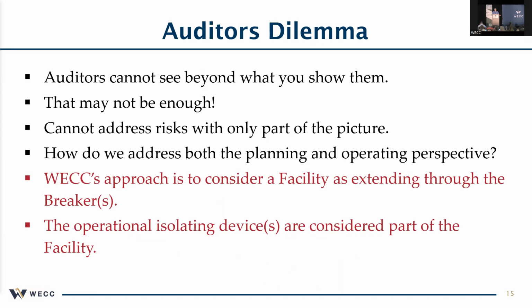Auditors don't get a comfortable feeling if you say, well, this is the rating that we're providing and it's only going halfway down this line. Do you agree with your partner? Is that the real rating? Does a person on the other end have a different rating? So our process in WECC, and I think the rest of the regions are, in fact, I know the rest of the regions are on board with this. They want to look at that whole facility on a transmission basis. They want to see the whole facility going from one place to another and make sure both entities coordinate and agree with that facility rating.